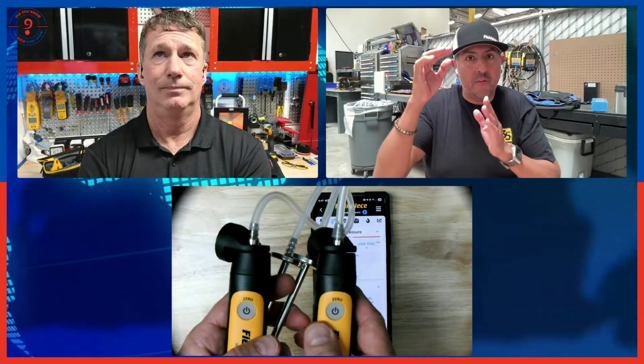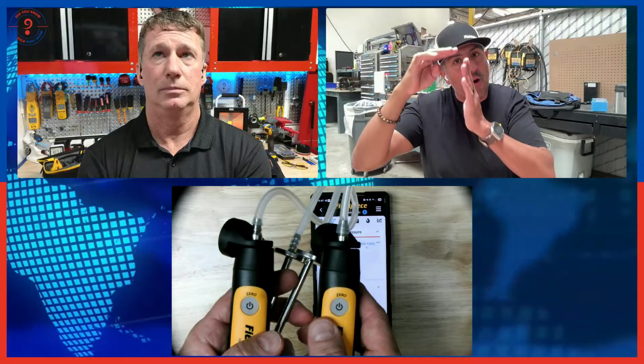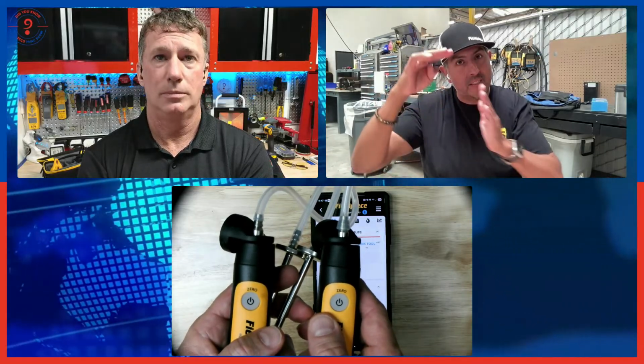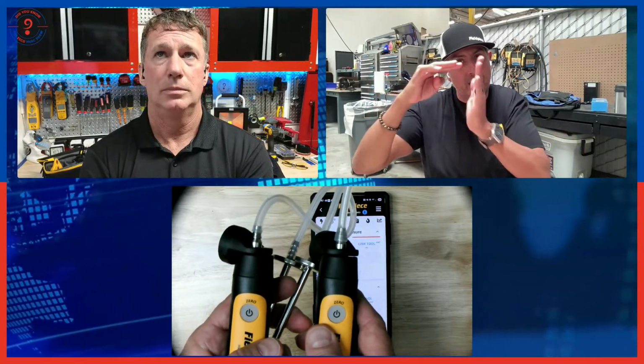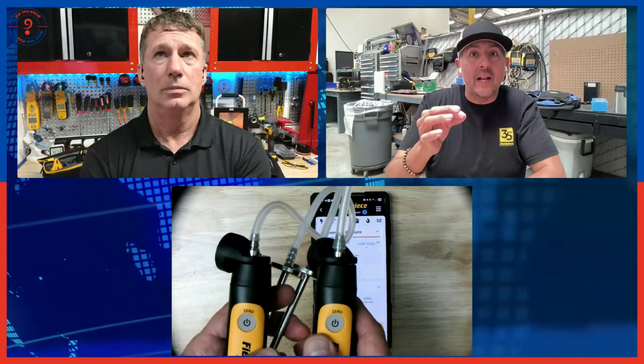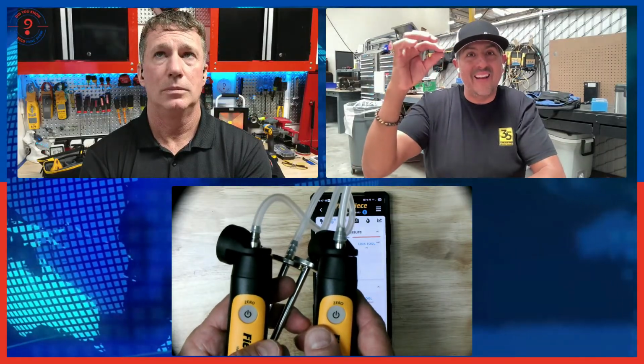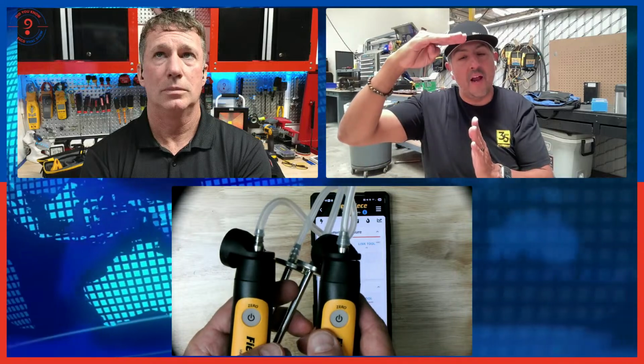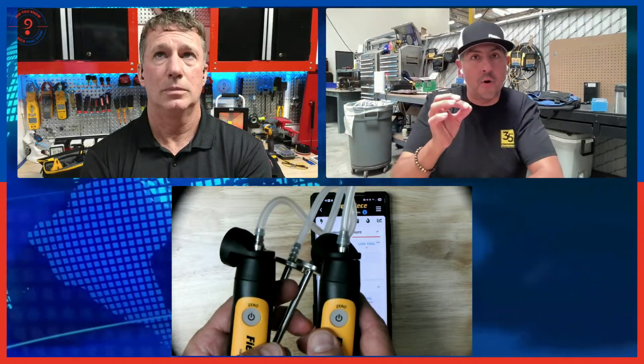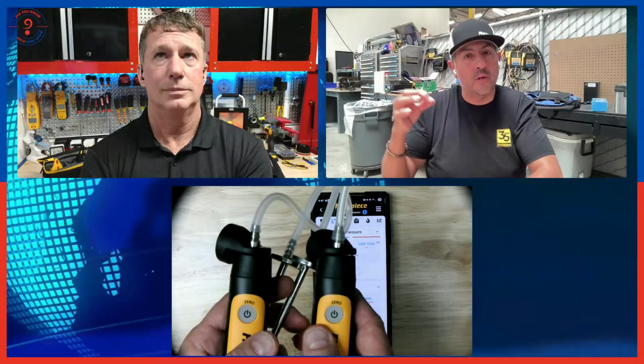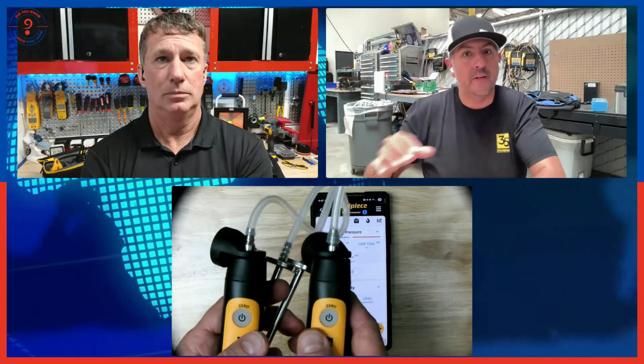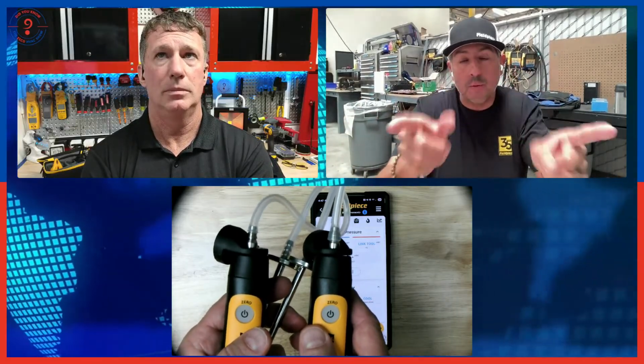We got to be very careful that we're getting air going directly across the opening of our tube versus at any direction in. So having that static pressure probe allows us to very easily ensure that we have air going across the holes in the probe and not directly into the hole, which would mess with the accuracy of our static pressure reading. Okay.